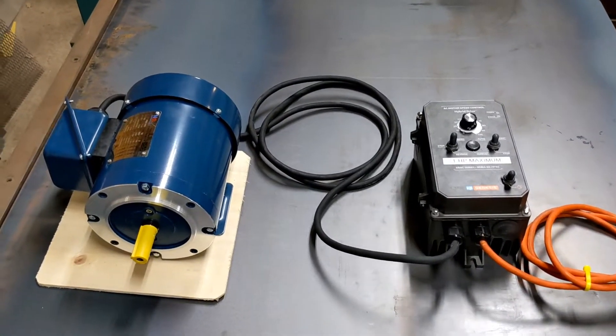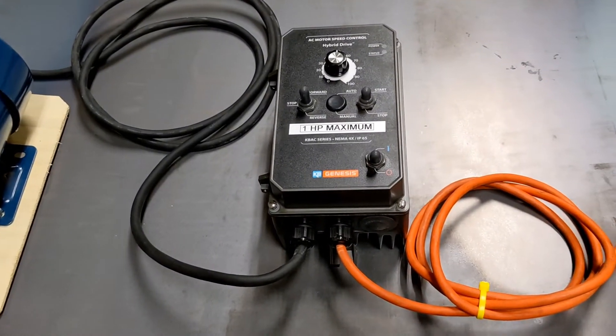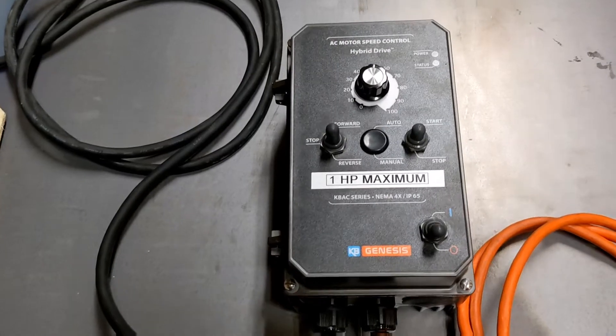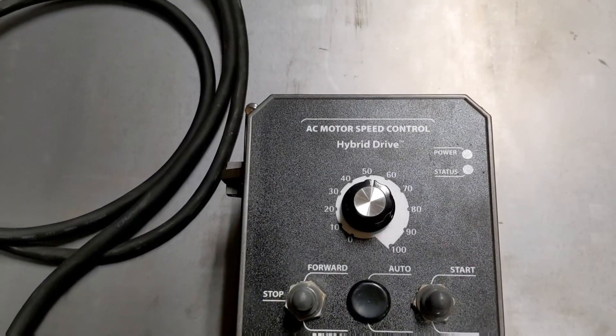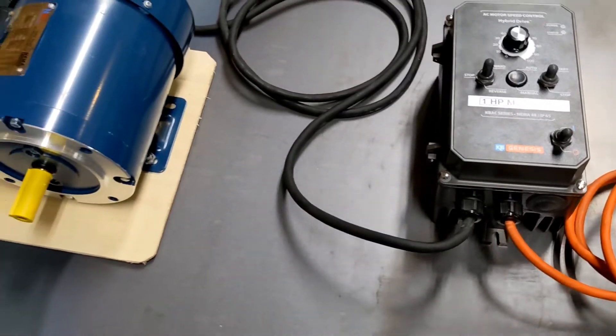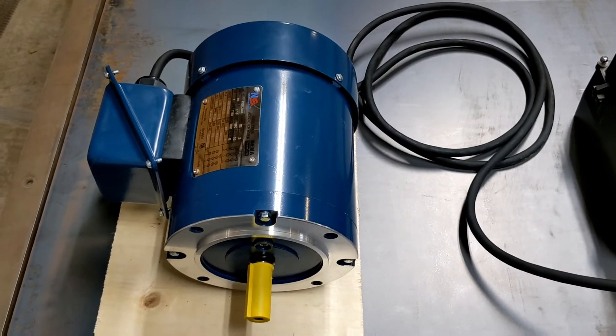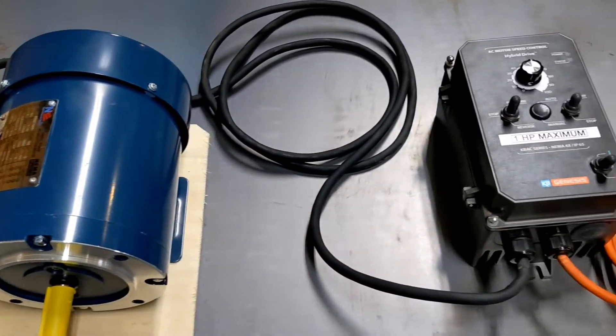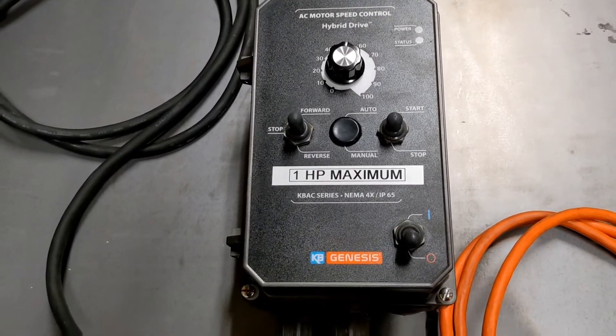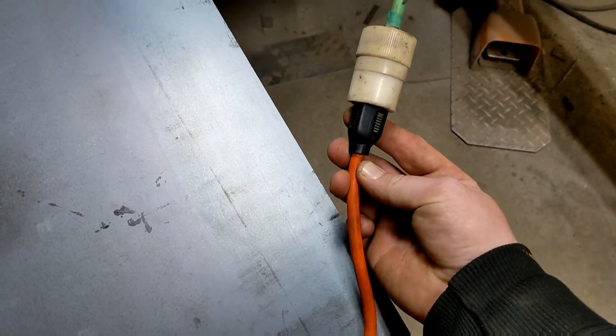Hello everyone, welcome back. Today I thought I would quickly go over a little bit of different content than is normally on the channel. I was going to show you guys this KBAC VFD drive. These things are very handy for updating drill presses or older machines that have three-phase motors that you need to run on 110 power. This unit can be run on 230 volt or 110 volt — we have this one set up for 110 volt right here.